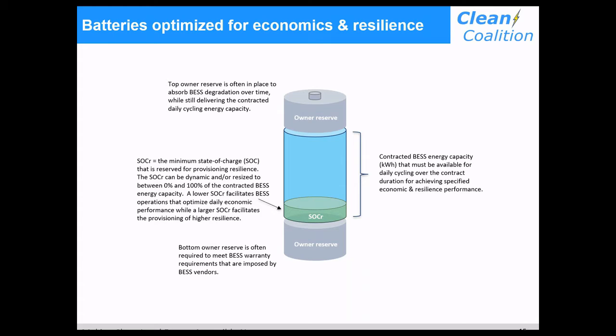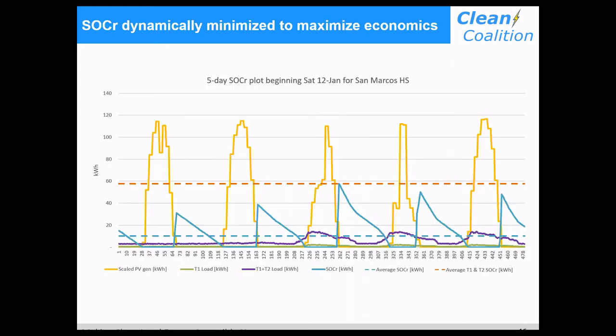That changes constantly. In this slide, the yellow is solar generation, and the blue is the SOCr level, which changes at every 15-minute interval. The Clean Coalition has developed a SOCr calculator that tells you, at every 15-minute interval, what the SOCr needs to be - if you lost the grid right at that moment, what does the SOCr need to be to ensure you can keep those tier 1 loads on forever. So it changes, and you can see it's a sawtooth pattern.